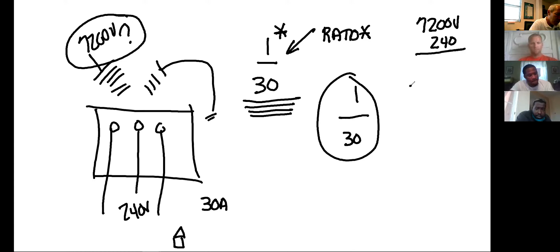Okay, so let's go this direction. I take a measurement and I've got 2 amps on the primary side. This is the high side. How many amps are on the secondary side? If I divide it going up, what do I need to do going down? Got to multiply it. So how many amps do I have on the secondary side? 60. Perfect.